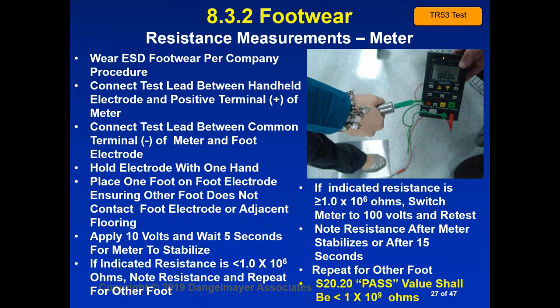So now, if we're going to do footwear measurements with a meter, you're going to first of all make sure that people are wearing their footwear per your company procedures. You're going to have a handheld electrode. You see that's the electrode the person is holding in their hand that has the green wire connected to it. You're going to connect a test lead between that handheld electrode and the positive terminal of your meter. Then you're going to connect a test lead between the common terminal of the meter and the foot electrode. You see that foot electrode that's on the floor there. Then you're going to hold the electrode in one hand and place one foot on the foot electrode. The other foot has to be up in the air. You don't want it to contact the electrode or the adjacent flooring.